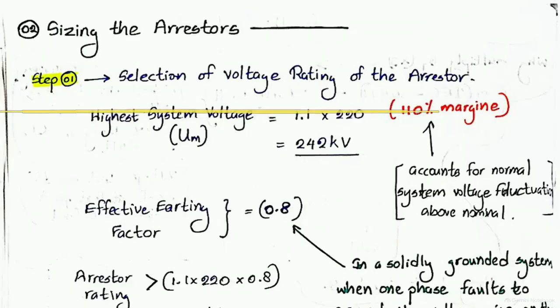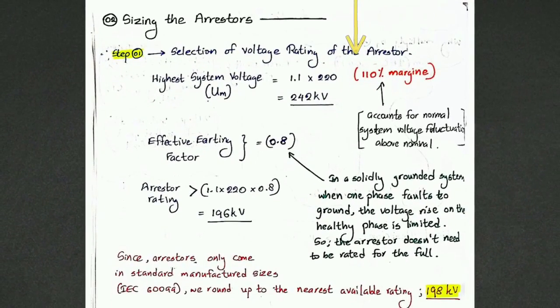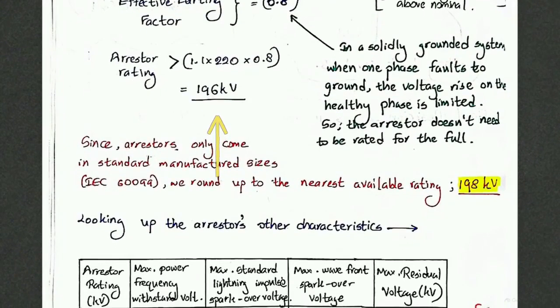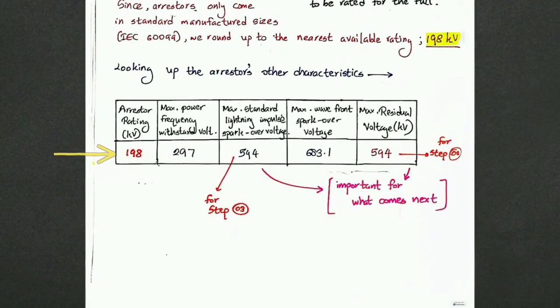Now we move to the second bodyguard, the arrestor. Step 1 is determining the voltage rating. We multiply our 220 kV system by a 110% safety margin, then by an effective earthing factor of 0.8. That gives us a minimum rating of 196 kilovolts. Because these components are manufactured in standard sizes, we round up to 198 kilovolts to ensure we meet the requirement.